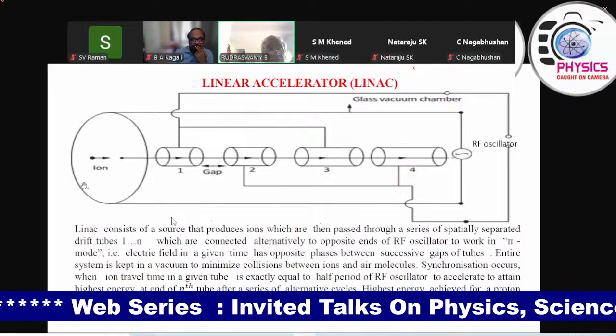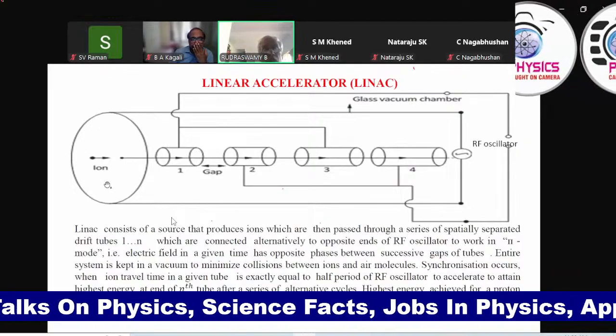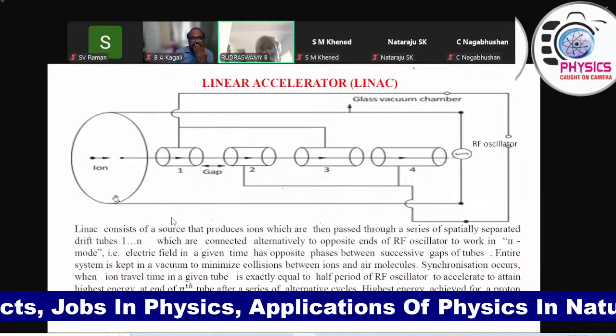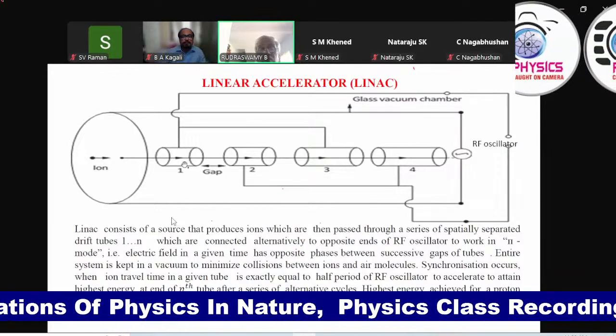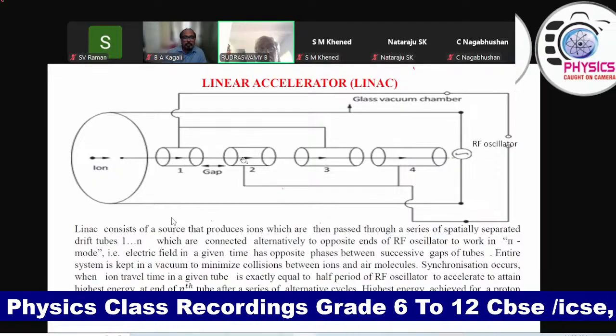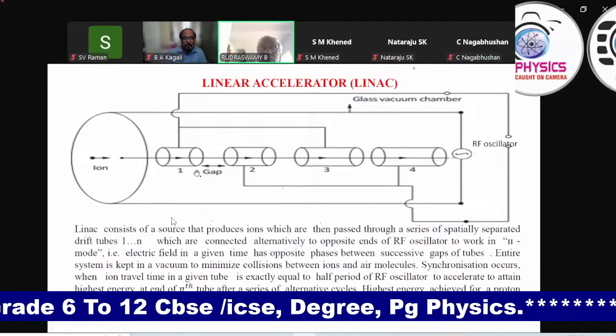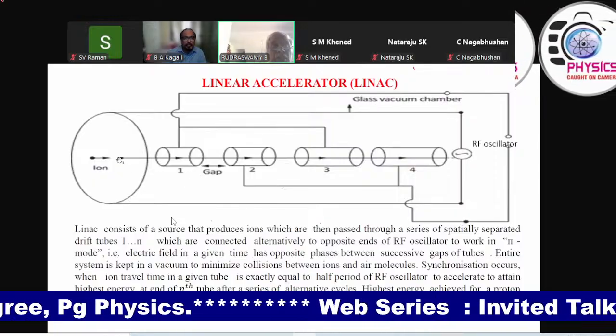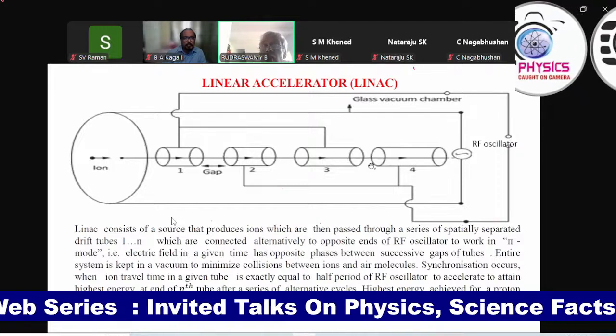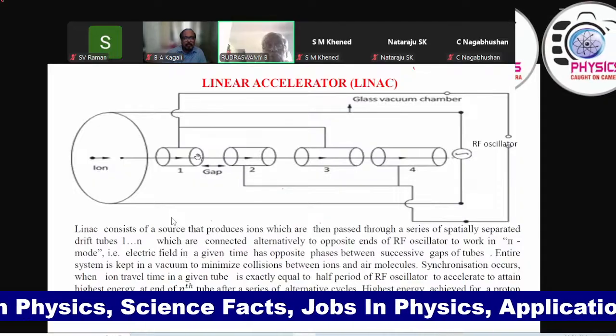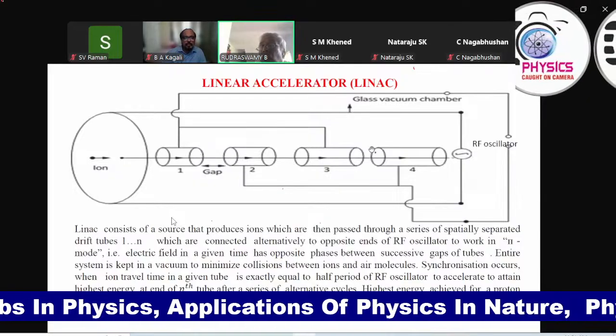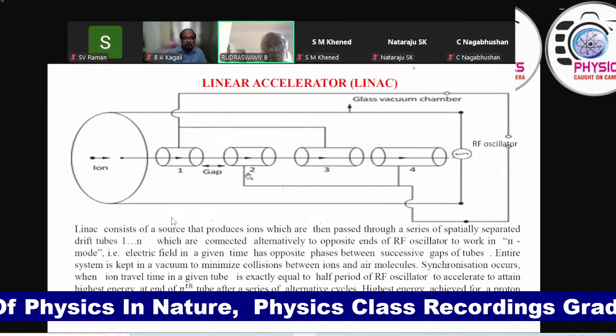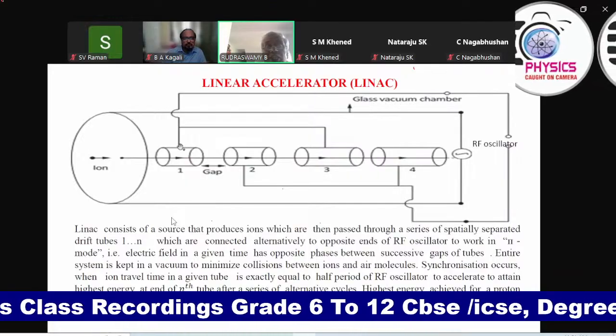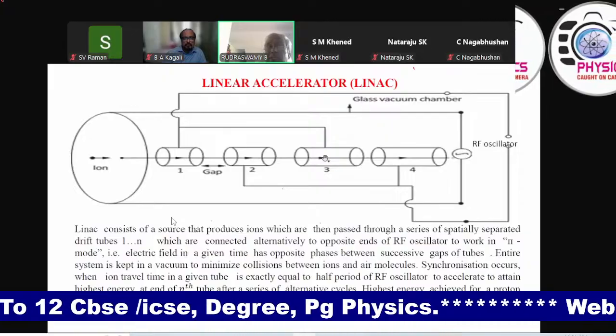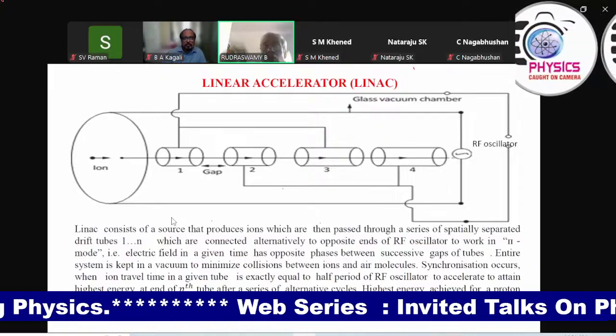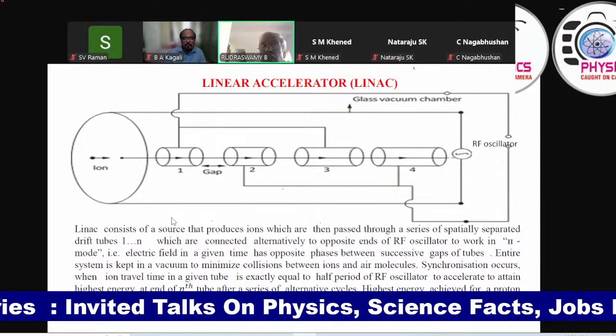So the LINAC consists of this source position, and you can produce variable ions at this point and pass them through these tubes. They are called drift tubes. In fact, their lengths are increasing here. The ions are passed through these drift tubes. And one thing you have to understand here: these alternate drift tubes are connected to the RF oscillator. The first, third, fifth, likewise, if you have n number of tubes, you can connect the odd ones to one end of the RF oscillator, and the even tubes to the other end.